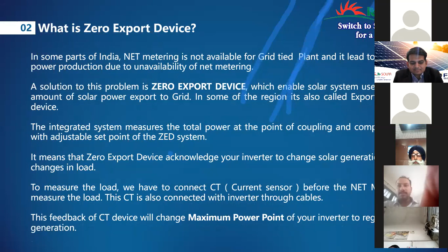So the solution to this problem is the zero export device, which enables the solar system to limit the amount of solar power exported to the grid. It is also called the export cutoff device. The zero export device tells your inverter to change the solar generation as per the change in the load. To measure the load, we have to connect the CT before the net meter.